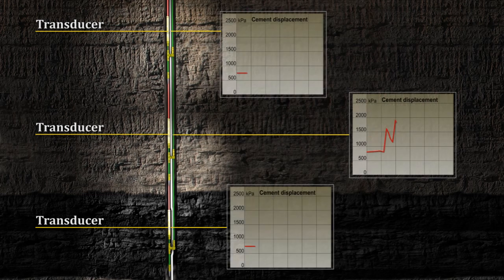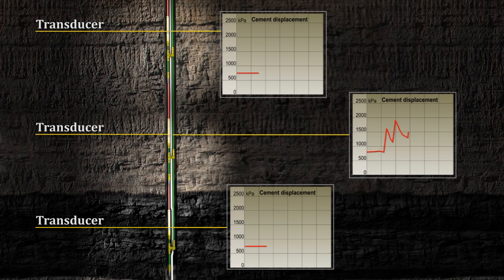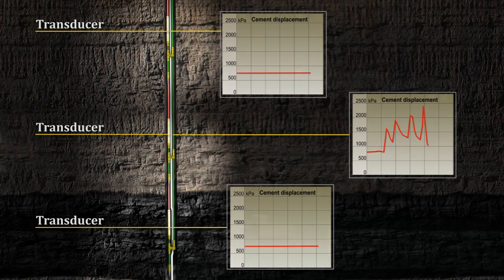No pressure response in transducers above and below the one being tested indicates no connectivity between transducers within the borehole. The above two tests validate the installation.